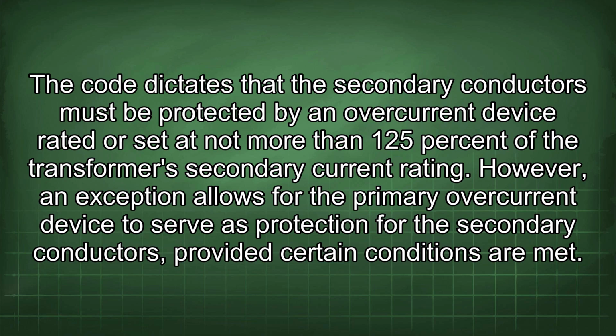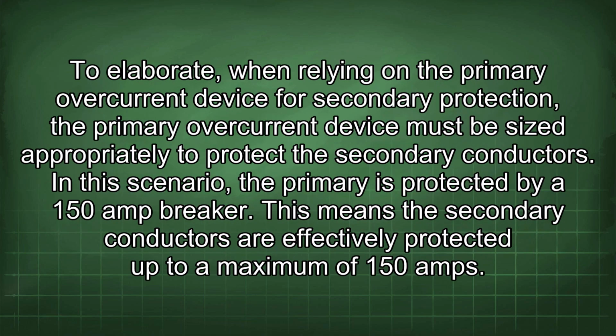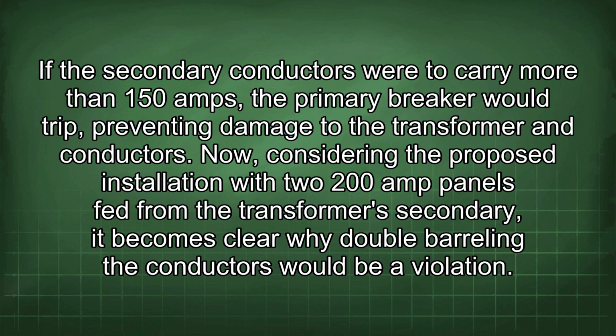However, an exception allows for the primary overcurrent device to serve as protection for the secondary conductors, provided certain conditions are met. To elaborate, when relying on the primary overcurrent device for secondary protection, the primary overcurrent device must be sized appropriately to protect the secondary conductors. In this scenario, the primary is protected by a 150-amp breaker. This means the secondary conductors are effectively protected up to a maximum of 150 amps. If the secondary conductors were to carry more than 150 amps, the primary breaker would trip, preventing damage to the transformer and conductors. Now, considering the proposed installation with two 200-amp panels fed from the transformer's secondary, it becomes clear why double-barreling the conductors would be a violation.